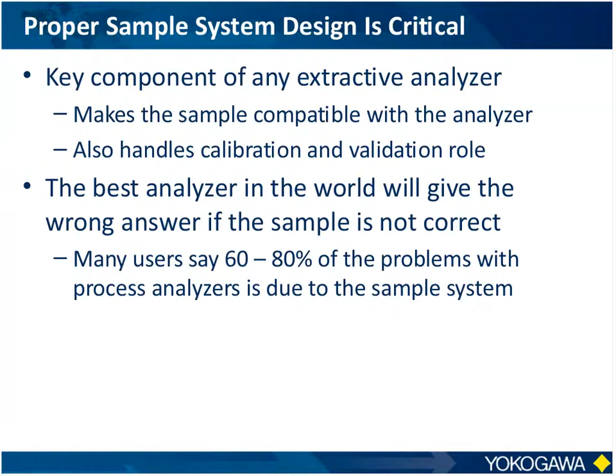So when you're dealing with a system integrator that does your shelters or your boxes, your cabinets, one of the things you want to make sure you do is you chat with them about how much experience they have, not just with the shelter design aspects itself, but the sample conditioning aspects. Because again, the whole idea is you're trying to have analyzers to use. And if you're not getting the right sample to the analyzers, you're going to have a lot of headaches.